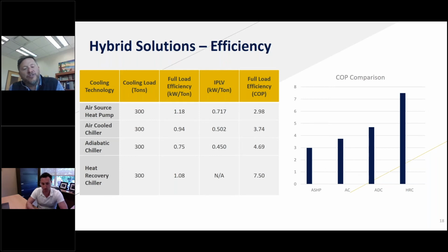And so, if I say simultaneous, that really talks about, well, let's say we can look at a heat recovery chiller. There are some air source heat pumps that have the ability to build that into them, but even for ones that don't, we can now actually have a separate dedicated heat recovery chiller based on our load profile. And if we can capture the simultaneous load that is pretty much year round, well, now we can actually start to take that load off of an air source heat pump system and put it in a heat recovery chiller.